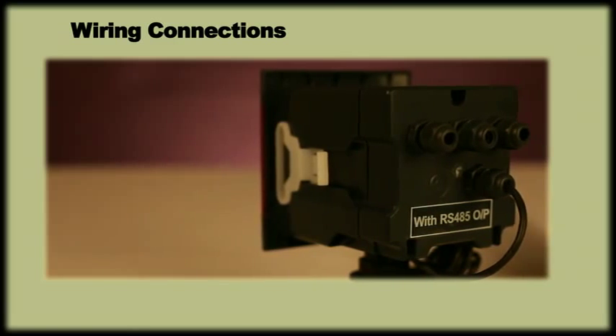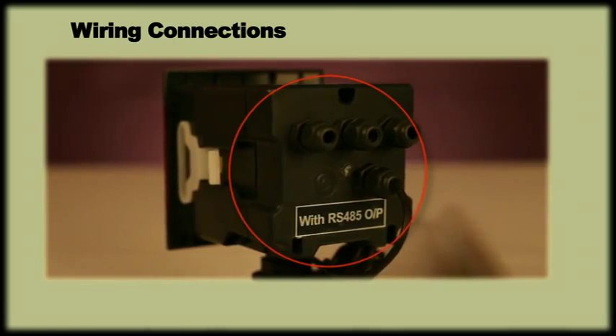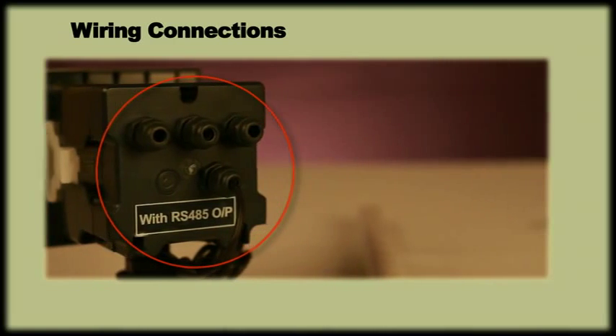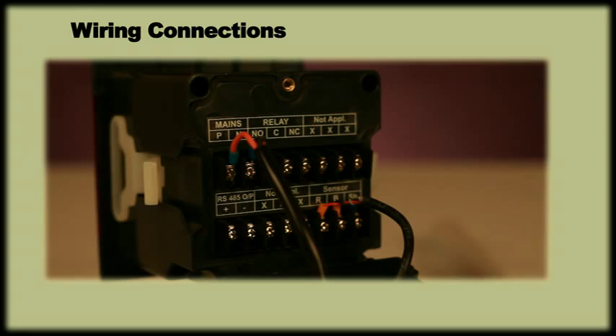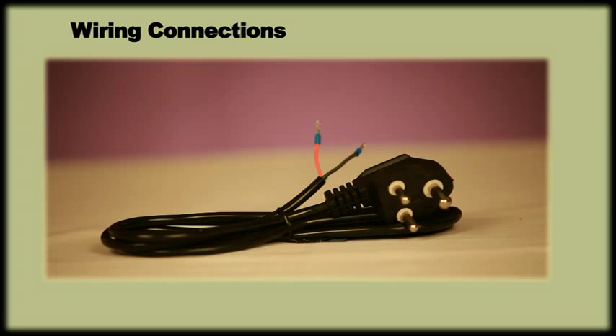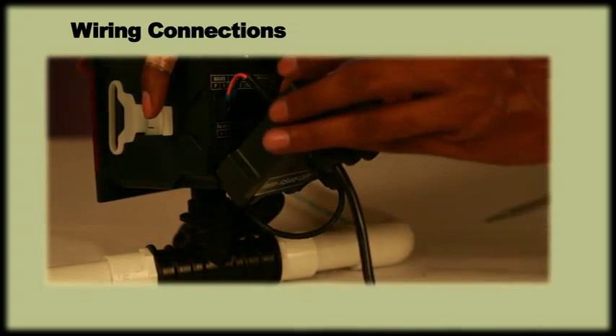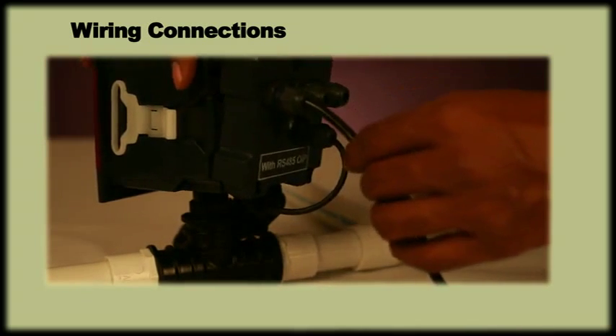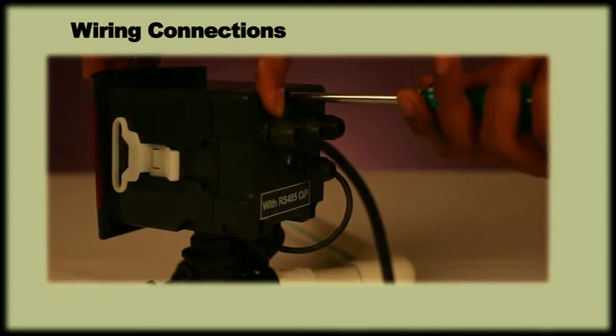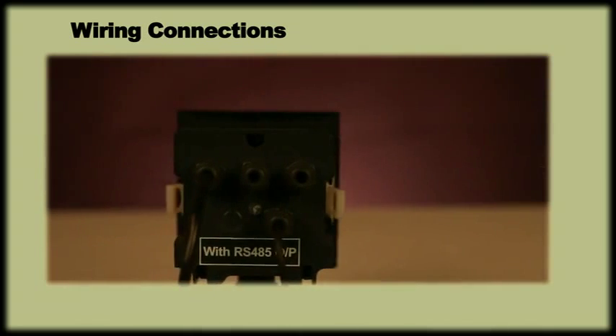Wiring connection. The meter has glands on the hinge cover to route the mains cable and output wires to their respective terminals. The supply voltage should be 230 volt AC plus or minus 10% unless specified. The cable used must be round and of 6 to 8 mm in diameter. While closing the hinge cover, any extra length of cable has to be pulled out of the glands such that the hinge cover can be closed tightly, keeping it IP65.